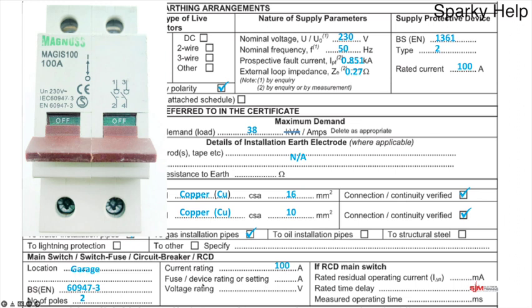When we go to fuse device rating or setting, well, this particular device is just an isolator, so it's no different to a light switch in that sense. If you get a fault on a light, the light switch will not turn off. This would be no different, so it doesn't have a fuse device rating or setting, so that gets an NA. Because if we look back here, it said it could be a switch fuse or a circuit breaker, and obviously they would have a device rating or setting.